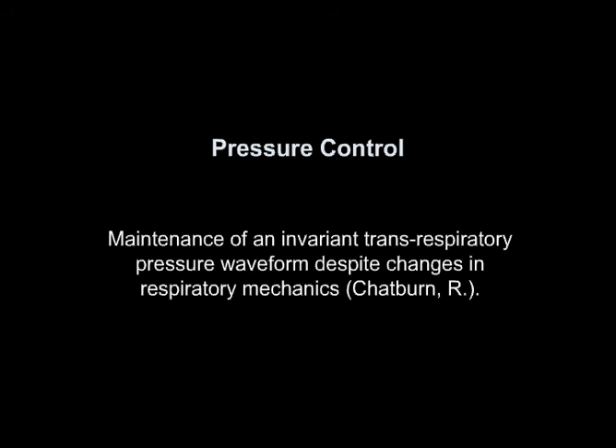Next, pressure control. With pressure control, the ventilator is trying to maintain a pressure waveform despite changes in the respiratory mechanics.